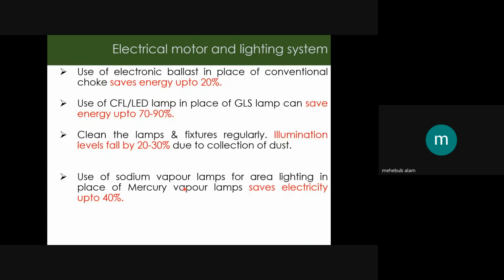For illumination and lighting systems, we have to use CFL or LED lamps in place of GLS lamps. We have to clean the lamps and fixtures regularly, and it will also improve illumination performance. Also, use sodium vapor lamps for large area lighting, and we can replace the mercury vapor lamp with the sodium vapor lamp, and there is a potential saving of up to 40%.